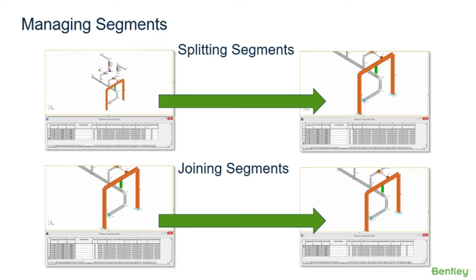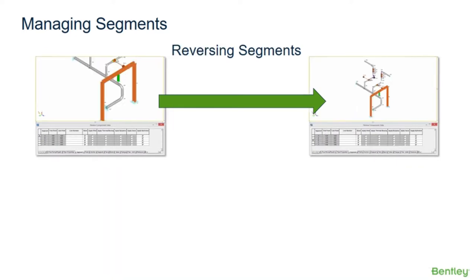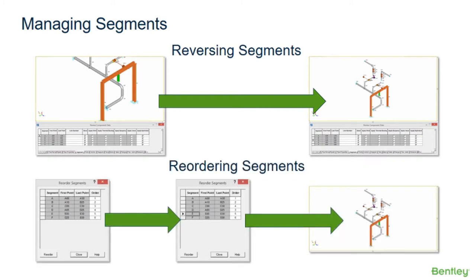The join segment command will merge two segments at a junction or continuation point. Merging segments allows fewer segments and simplifies the model when segments have been reconnected back at a junction or continuation point. The reverse segment command will reverse the direction of the current segment and renumber it if it has alphanumeric numbering. This is very useful when importing CAD models, where the sequence the CAD model was built in is often unorganized. Reversing segments also improves the ease of working with the model, such as inserting components in a forward segment direction.